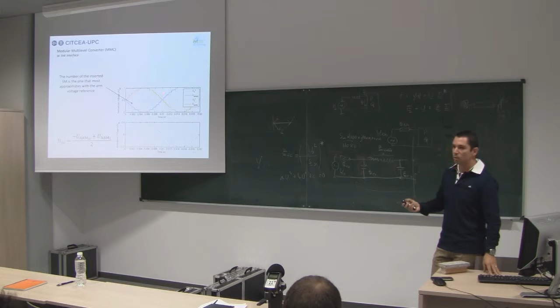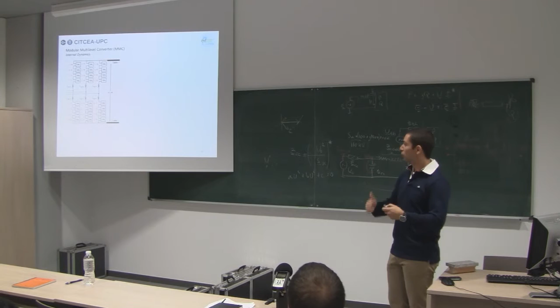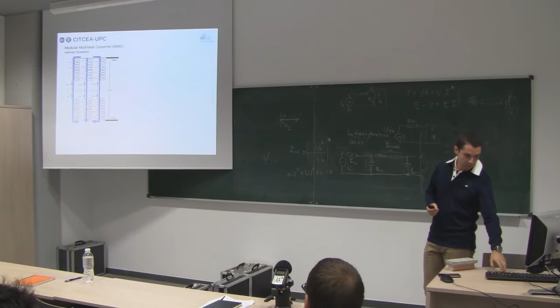Regarding the internal dynamics of the converter, since you have hundreds of submodules, it's normal that at some moment conditions aren't nominal. It can be normal to have one capacitor more charged than another, one phase unit more charged than another, and so on. With this converter, you also have internal currents flowing between phases so that you balance the phase units and the arms.